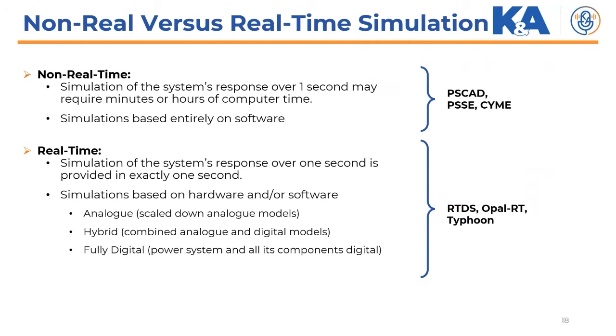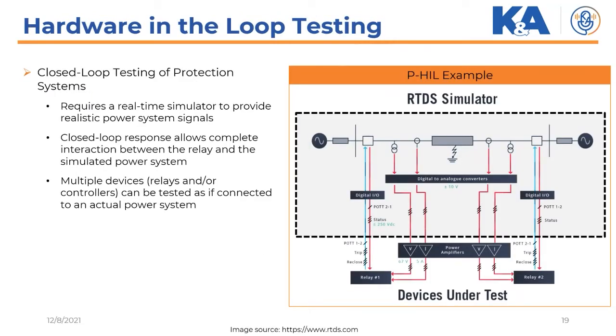Now, in the next slide, here in this graph, you can see we have a small system, two generators, one transmission line. We are getting some signals from the side of the transmission line, converting them to actual signals and then giving them to a power amplifier, converting those to actual voltage and current and giving those voltages and currents to the relay. And the response of the relay will be fed back to the network. This is a hardware in the loop. Since the simulator is capable of performing on a real-time base, we are capable of doing such experiments or such sorts of studies. This has proved to be very useful in terms of testing different devices and different concepts, and is one of the main features of this tool.